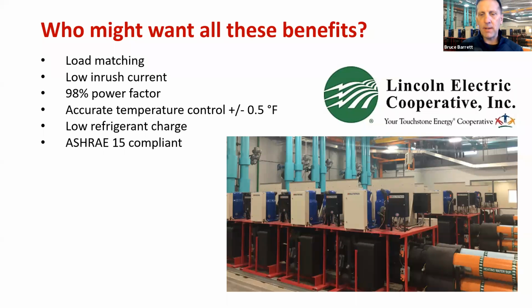All right, so that same heat recovery concept is employed for centralized geothermal heater chillers. We're simply using the heat of compression when we have the opportunity to do simultaneous heating and cooling. When we employ the variable speed compressors like we did in this job, Lincoln Electric service, very nice job, one has to think, why did the electric cooperative pick variable speed compressors? Well, they understood the low inrush, the great power factor. They're the utility company. They want to keep inrush low. And they wanted to leverage simultaneous heating and cooling in a geothermal environment.